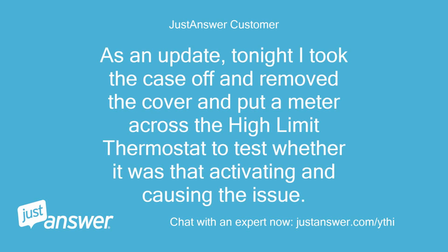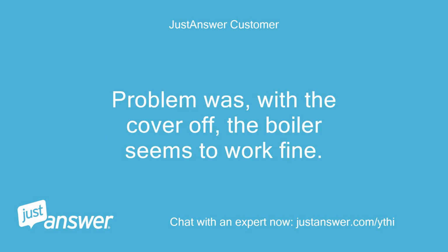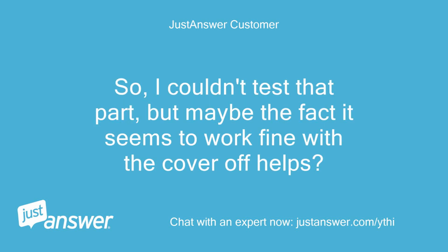As an update, tonight I took the case off and removed the cover and put a meter across the high limit thermostat to test whether it was that activating and causing the issue. Problem was, with the cover off, the boiler seems to work fine. So, I couldn't test that part, but maybe the fact it seems to work fine with the cover off helps?